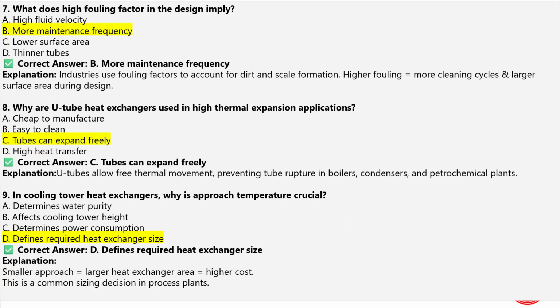So what does a high fouling factor in design imply? A high fouling factor means more maintenance frequency. Industries use fouling factors to account for dirt and scale formation. Higher fouling means more cleaning cycles and larger surface area during design, because in industry it's not always the case that clean water or the clearest form of liquid is moved through the heat exchangers. So that's why fouling factors are provided, and a high fouling factor clearly specifies that the maintenance frequency will be more.